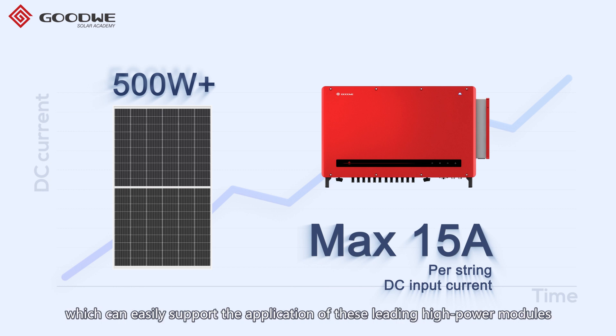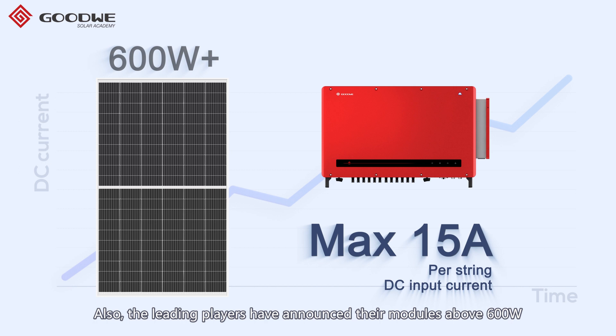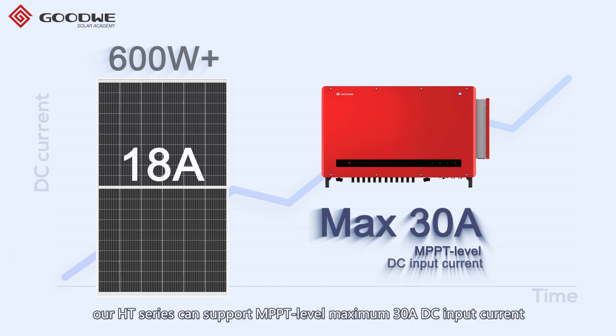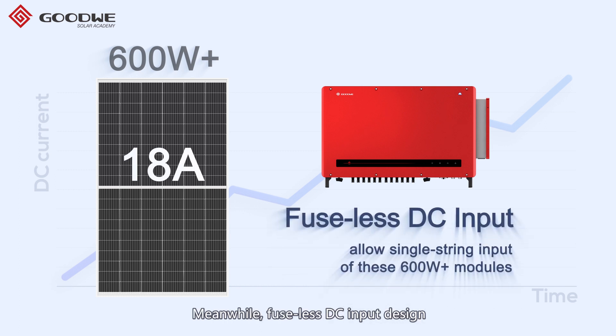Leading players have also announced modules above 600 watts with relatively higher DC current around 18 ampere. Our HT series can support MPPT-level, maximum 30 ampere DC input current. Meanwhile, the fuseless DC input design allows single string input for these modules above 600 watts.